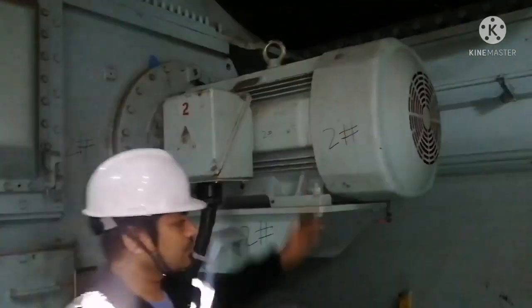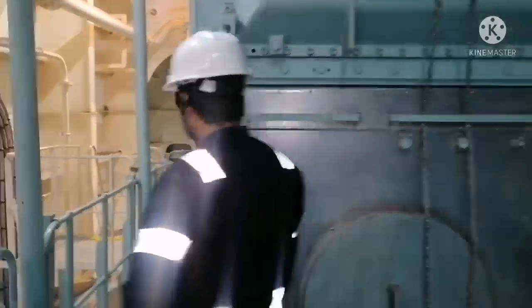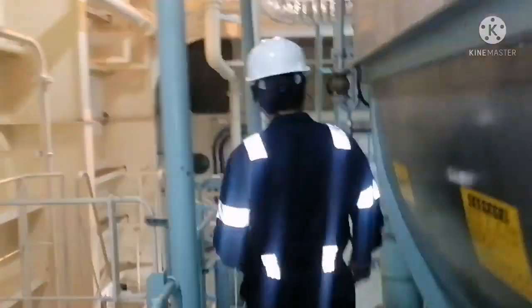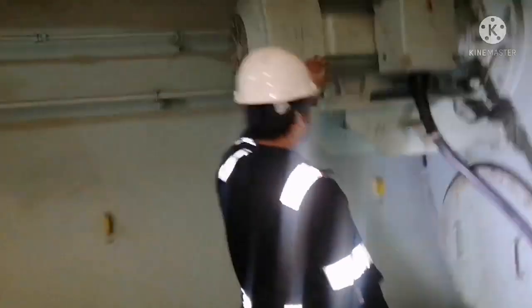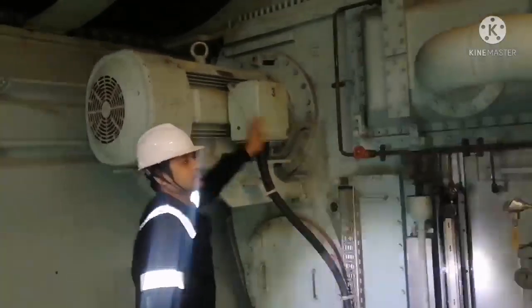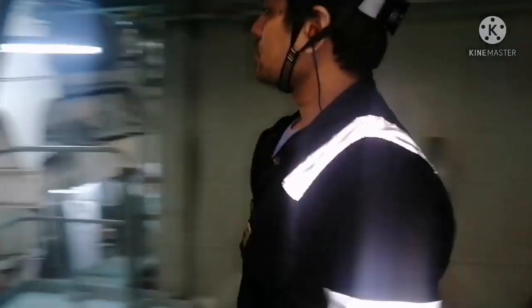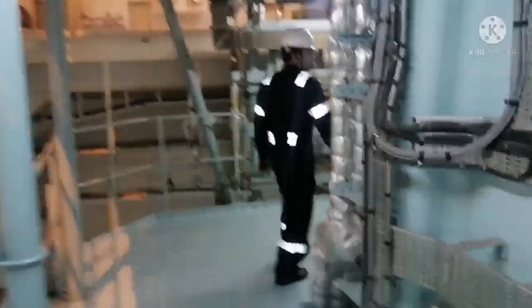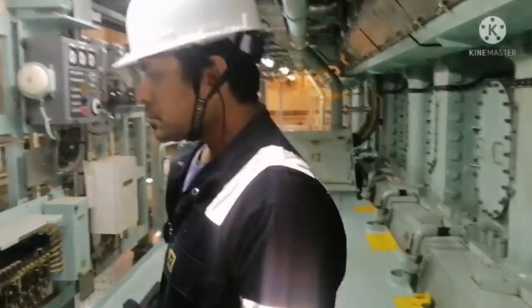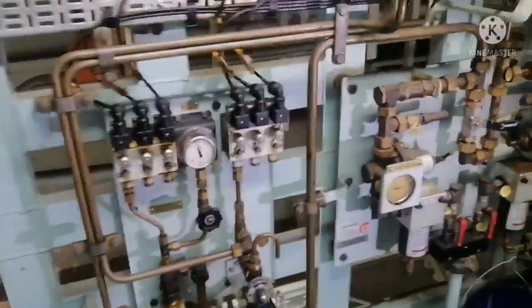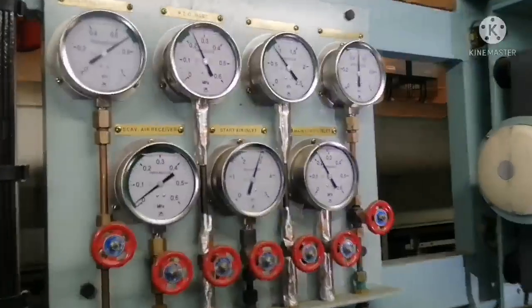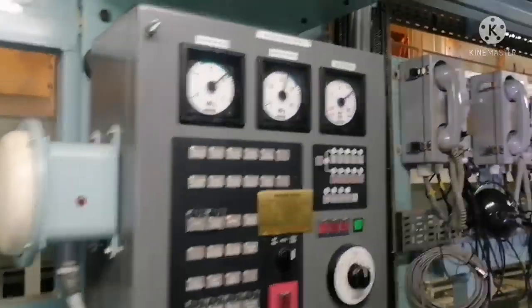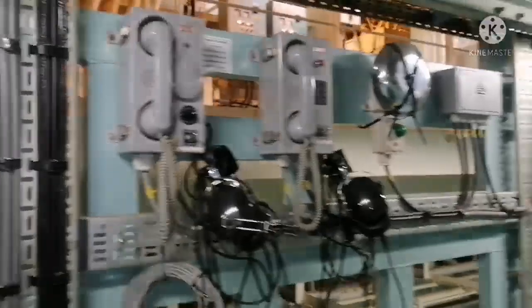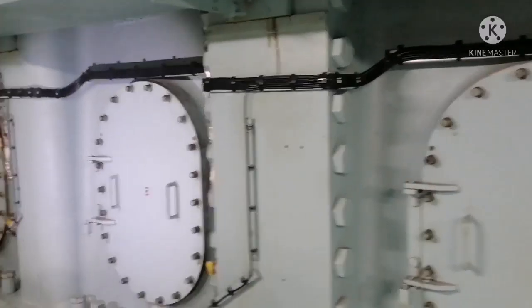So all the 3 blowers you need to check visually here for any abnormal noise, and you can feel for any abnormal temperatures over the motor. So I feel everything is okay, so I'm done with that. So I'll come to the opposite side. This is your emergency maneuvering platform. You just check that all temperatures and pressures are okay, no leakages, all pressure gauges are within the green zone. And this is your emergency telephone and everything.